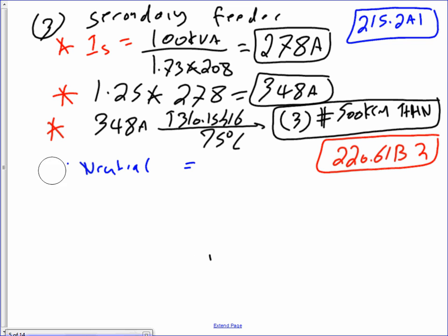The second thing I'm going to do is the neutral, guys. I need to size the neutral. I'm going to do it in a different color. My neutral feeder. For a neutral feeder, because you don't have what the neutral load is, it's just a transformer. You have no idea what the neutral load is. With me, guys, remember when you calculated the neutral load and you sized it based on that load? Do you have an idea what the load is here? I don't have any idea what the load is.